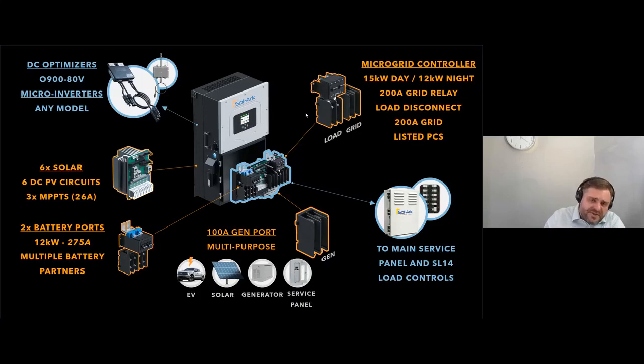You can divide the array across multiple roof surfaces instead of being very constrained on larger solar arrays by where you can place them. I've looked at string sizing for Sol Ark inverters and for other 12 kilowatt hybrid inverters that say they have 3 MPPTs, but 2 are smaller than the other. The constraints you get with circuit sizing will limit your module selection and your rooftop layouts, unless you have those full-sized MPPTs. With Sol Ark, no matter what module you're using, no matter what your roof looks like, you have very flexible options, meaning you don't have to use a different product for a different job.